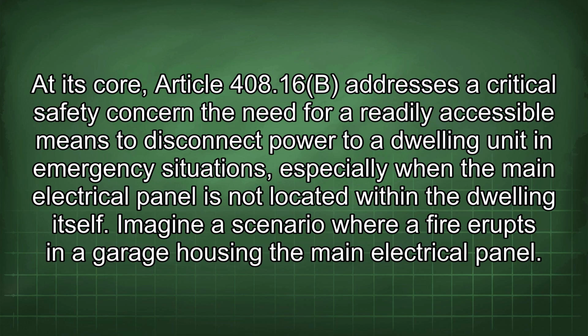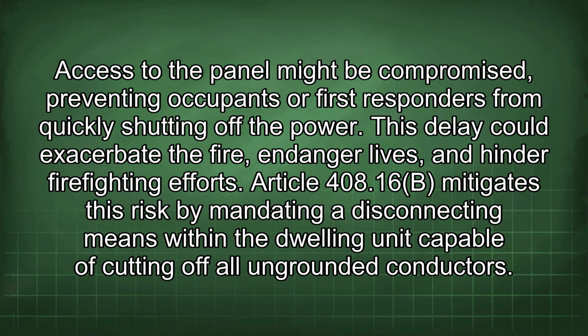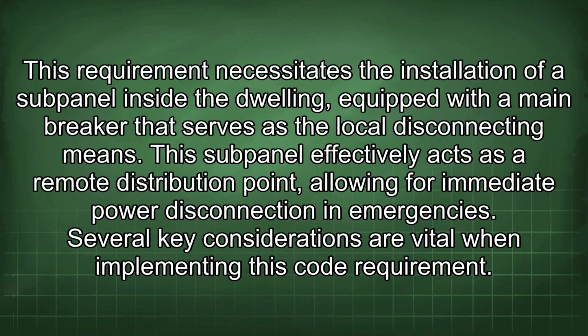Imagine a scenario where a fire erupts in a garage housing the main electrical panel. Access to the panel might be compromised, preventing occupants or first responders from quickly shutting off the power. This delay could exacerbate the fire, endanger lives, and hinder firefighting efforts. Article 408.16(B) mitigates this risk by mandating a disconnecting means within the dwelling unit capable of cutting off all ungrounded conductors. This requirement necessitates the installation of a subpanel inside the dwelling, equipped with a main breaker that serves as the local disconnecting means. This subpanel effectively acts as a remote distribution point, allowing for immediate power disconnection in emergencies.